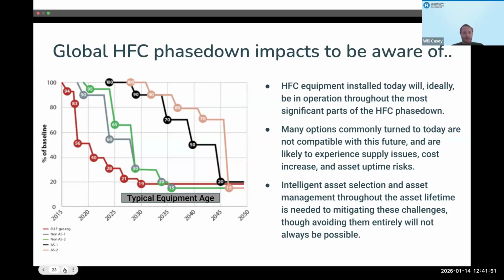Depending on the region, phase-down schedules can vary quite significantly. However, as we've tried to signify with that typical equipment age box, realistically any equipment installed today, regardless of the region, is hopefully going to be in existence for a large part of that phase down. So these pieces of equipment, anything installed today or relatively recently, will rely on a steady supply of refrigerant throughout their lifetime to service leaks.